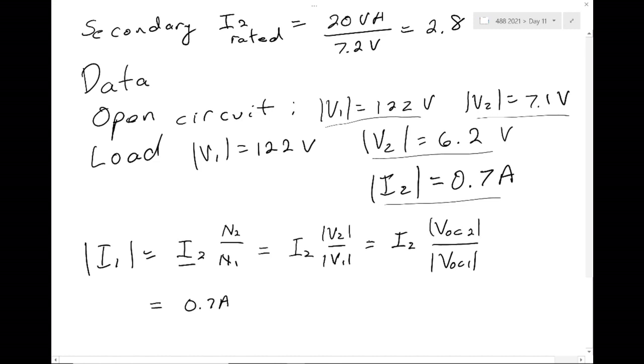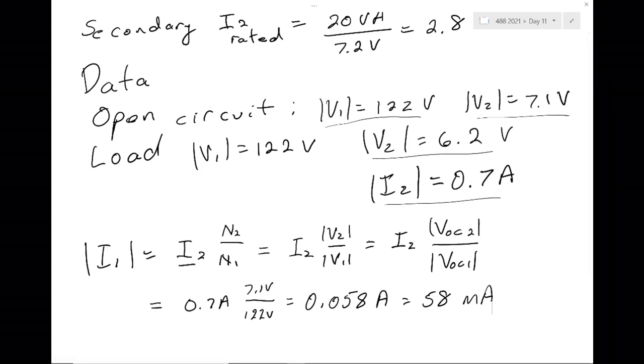So 0.7 amps times 7.1 volts over 122 volts gives me a value of 0.058 amps, or 58 milliamps, on the primary. 700 milliamps on the secondary, 58 milliamps on the primary.